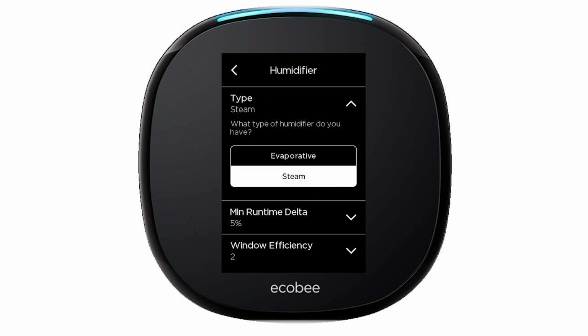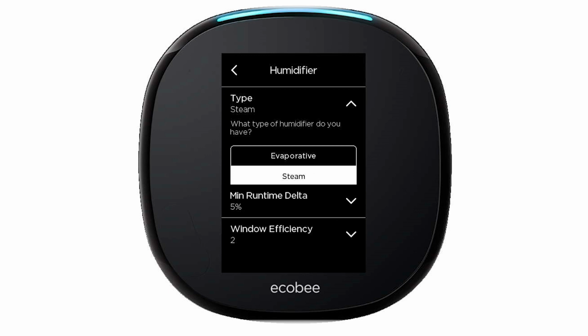If you go ahead and switch it over to steam, it doesn't matter if you have an evaporative humidifier or a steam humidifier. The only difference in the settings is that you will be able to continue running that humidifier whether or not there's a heat call. So that humidifier and the fan is going to kick on. It's going to maintain that humidity set point. It's not going to matter if the furnace is running or if there's a call for heat, right? So we always kind of recommend you use steam.